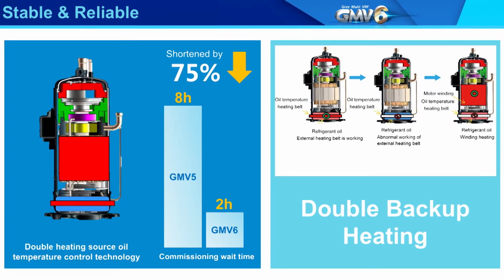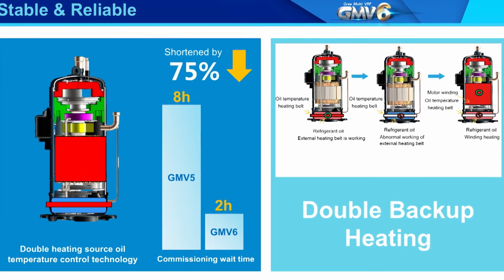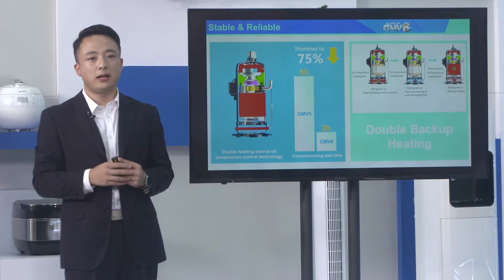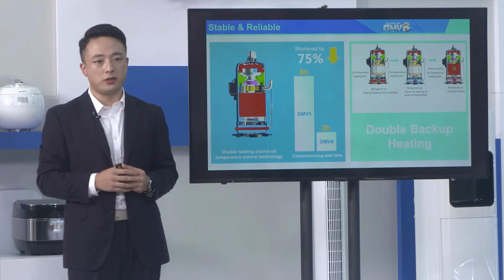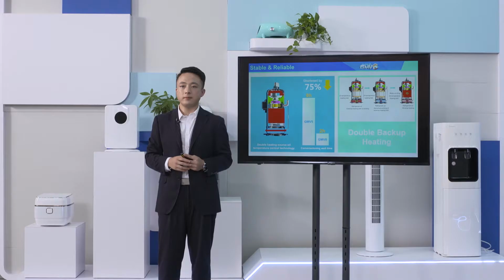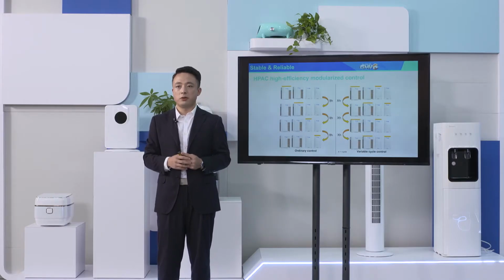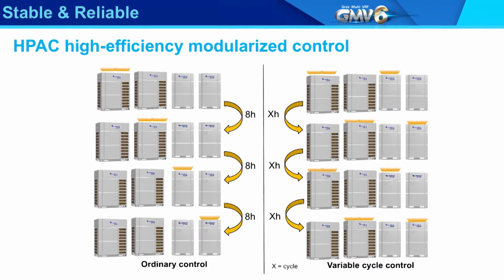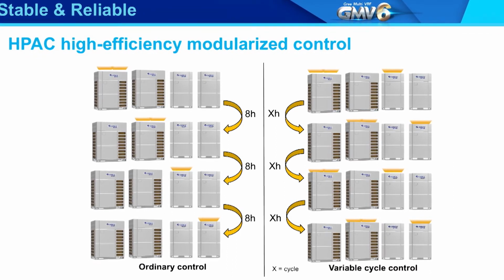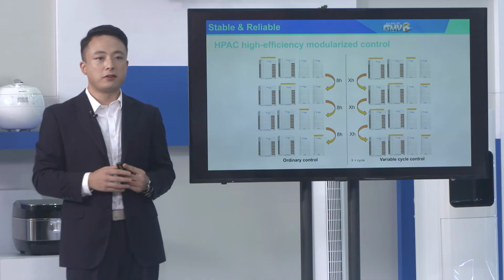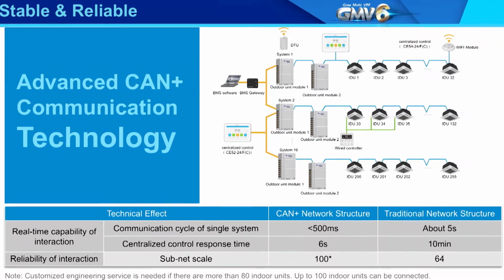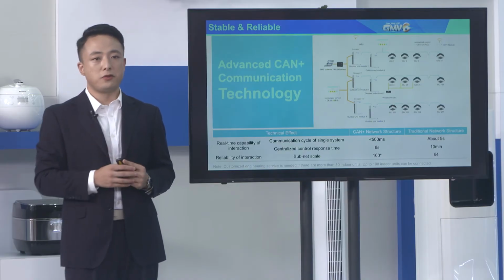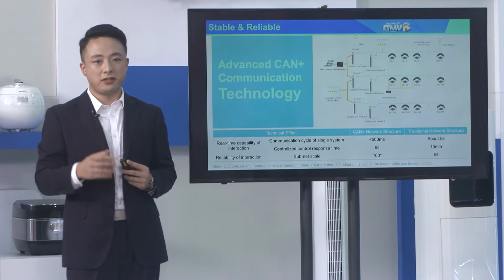Maybe you would like to know how GMV6 realizes stable and reliable performance. First, we adopt double heating source oil temperature control technology. Motor winding heating and the external electric heating work at the same time to accelerate the evaporation of refrigerant in the compressor when it is cold. Then, the variable cycle modularized control in every 8 hours based on the core performance of a high-efficiency compressor. It will balance the running time and load of each module to improve the overall lifetime of the entire system. Finally, we adopt the world-leading CAN+ communication technology. After upgrading, the number of nodes in one single system is increased by 56%.